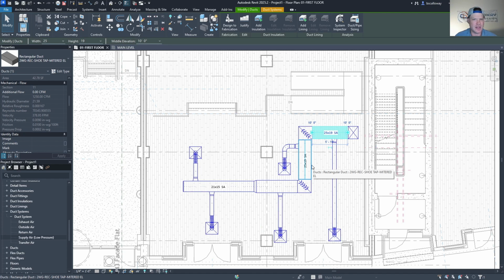So you know how much air you've got left, and for me, it helps me size it. I'll kind of come through here and do it like this. Now watch this—that's going to drop off. Now we're only picking up 1,000. Now we're only picking up 750, and now we're only picking up 500. So keep an eye on that because I think it helps tremendously. It also shows you your pressure drop, your velocity, a bunch of good information there.